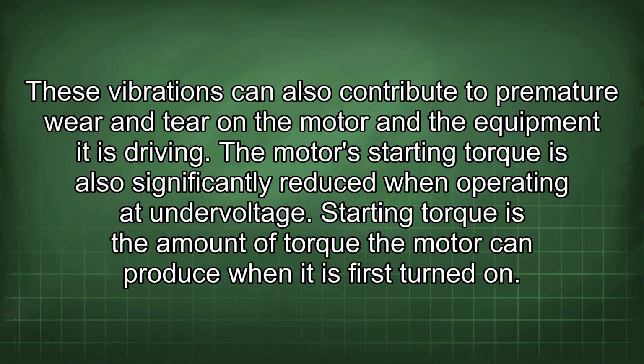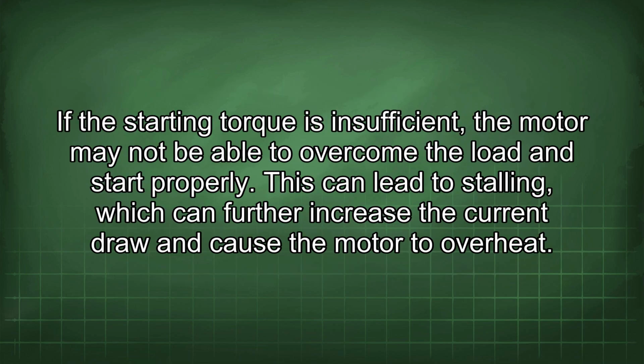The motor's starting torque is also significantly reduced when operating at undervoltage. Starting torque is the amount of torque the motor can produce when it is first turned on. If the starting torque is insufficient, the motor may not be able to overcome the load and start properly. This can lead to stalling, which can further increase the current draw and cause the motor to overheat.